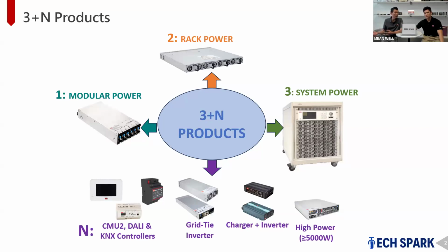And the combination part, that is the N. N is like an infinite combination. It has the intelligent control, CMU2, that you use along with our power supply to control and monitor. Or it has the DALI, we have DALI that controls the LED lighting. For example, a smart controller CMU2 can be installed inside a 19-inch rack to monitor and control 50 rack power units, the health of the power supply.